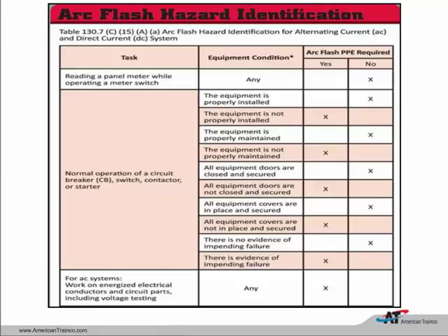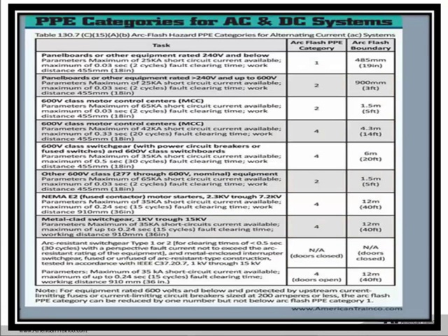So a couple scenarios we want to look at. The equipment was properly installed. It was properly maintained. All the doors and covers are secured. All the original hardware is in place. No evidence of impending failure. We do not have to wear arc flash PPE in that instance. But if one of those things is missing, then we would put on arc flash PPE to operate that equipment. Of course, if we do have something exposed, we know that we do have some hazards present immediately there, and we would have to wear the arc flash PPE that we're going to look at here in this next slide.